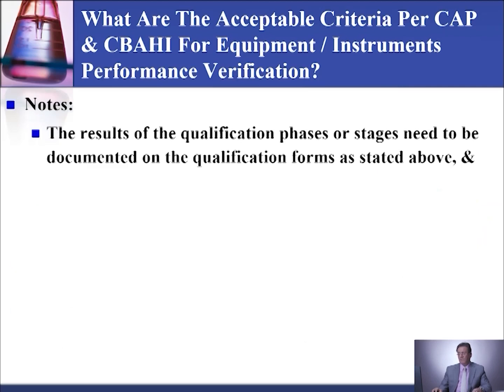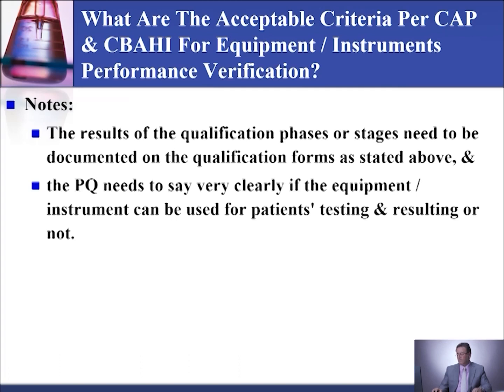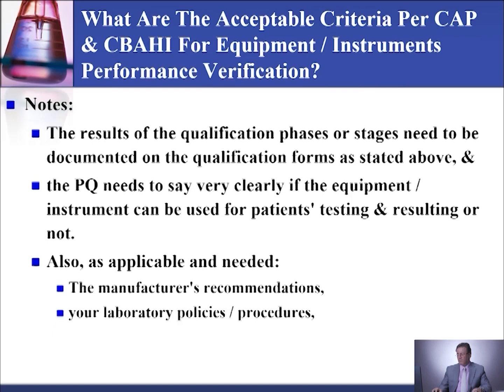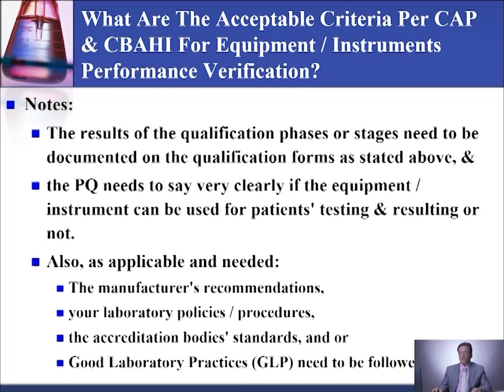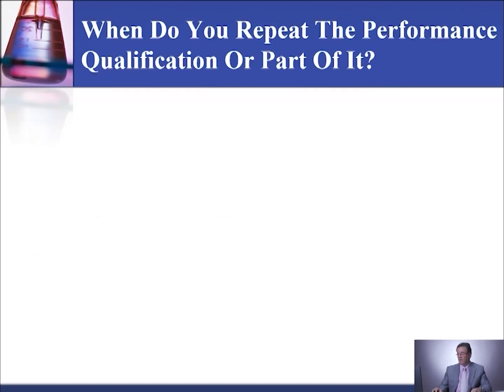Some notes regarding this item: the result of the qualification phases or stages needs to be documented on the qualification forms, as I stated before, and the PQ needs to say very clearly whether the equipment or instrument can be used for patient testing and resulting or not. Also, as applicable and needed, the manufacturer recommendation, your laboratory policy procedures, the accreditation body standard, and/or good laboratory practice need to be followed when you are doing the verification or a performance verification for the equipment or the instrument.